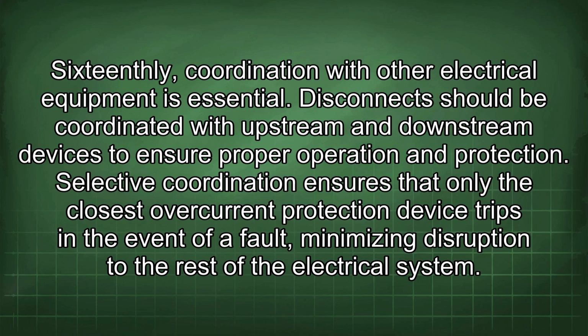16thly, coordination with other electrical equipment is essential. Disconnects should be coordinated with upstream and downstream devices to ensure proper operation and protection. Selective coordination ensures that only the closest overcurrent protection device trips in the event of a fault, minimizing disruption to the rest of the electrical system.